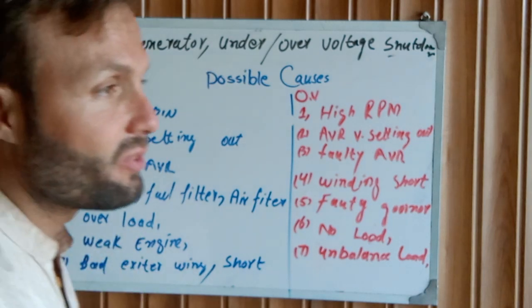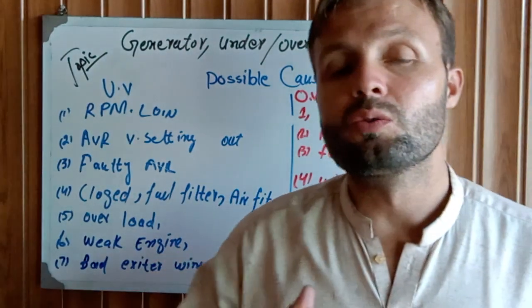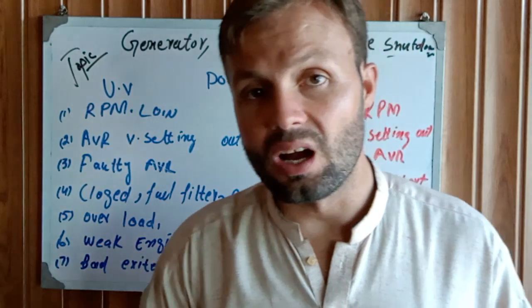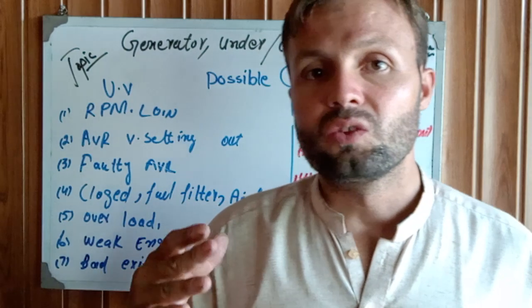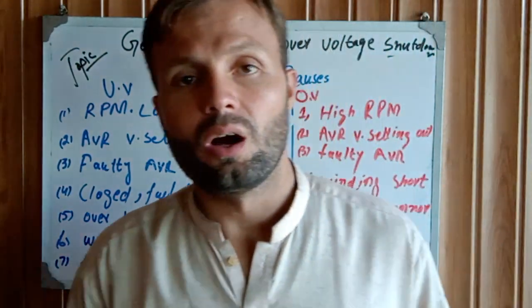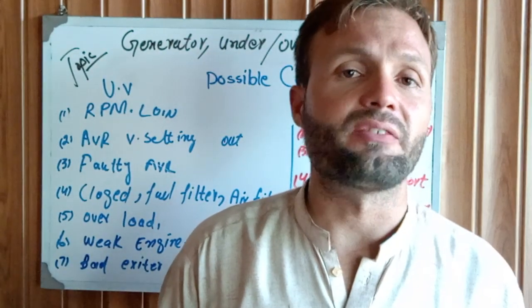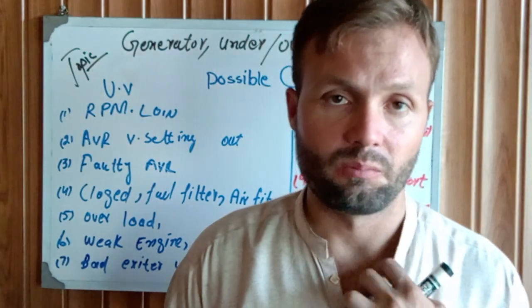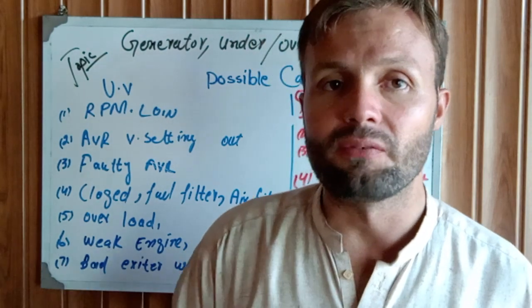Another cause is overload. If your engine is overloaded, the voltage drops and the engine RPM drops because too much load has been put on it. The engine cannot carry the overload. For example, if you have a 5 kilowatt generator, you cannot put 7 kilowatts of load on it — that means it is overloaded, which causes under voltage and the generator trips.